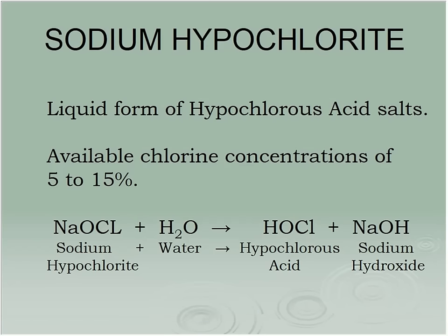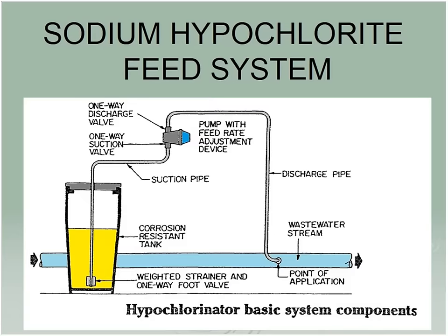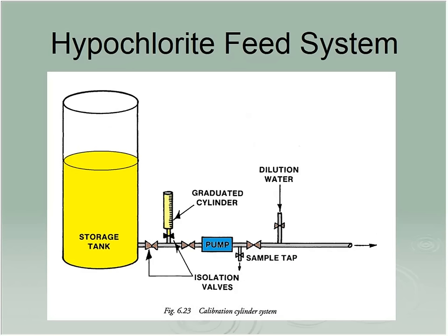Again, most people have abandoned liquefied chlorine gas in favor of sodium hypochlorite. Sodium hypo is just chlorine bleach, 5 times more concentrated, about 15% chlorine. Again, when you add it to the water, you're going to form that hypochlorous acid, keeping in that same pH range. But you don't have any gas clouds going away. You just have tank trucks rolling into your driveway or something like that. You've got a drum of material and a little metering pump, you can go and chlorinate any place you want. Works very well, easy to control.